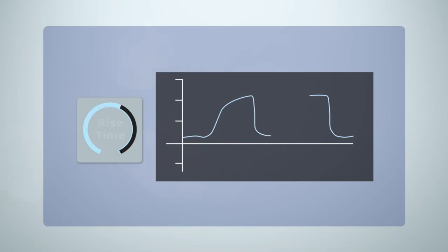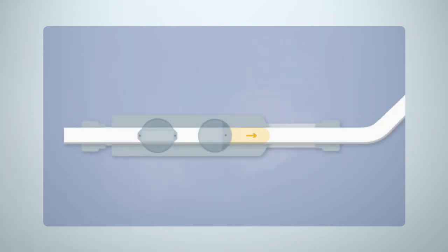There is also the option to shape and control each breath by adjusting the rise time as well as modifying the pressure of each pulse that is delivered to the patient. A consistent feature of any mode is a second forward-facing jet delivering optional CPAP or PEEP.